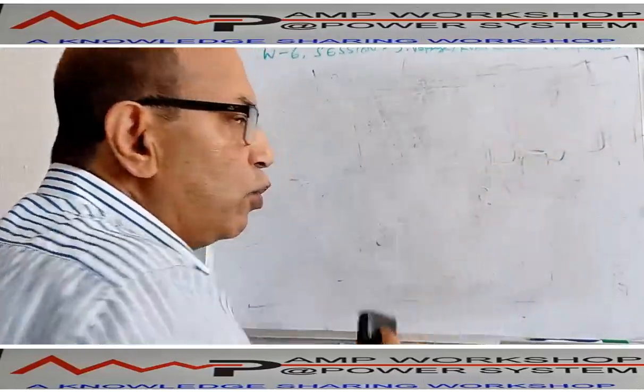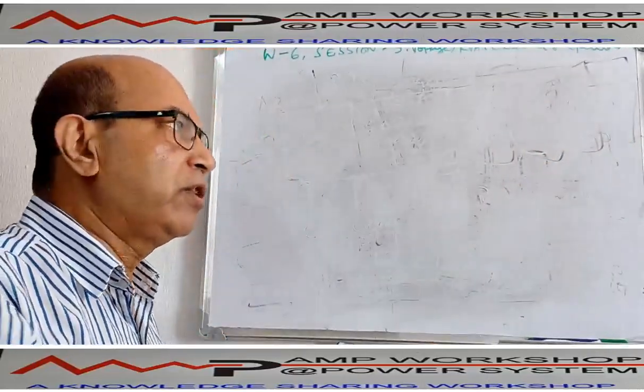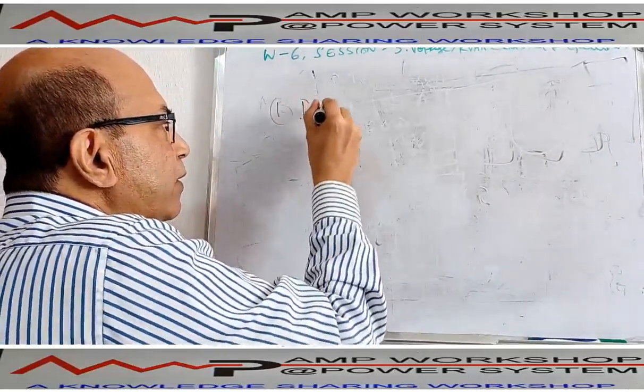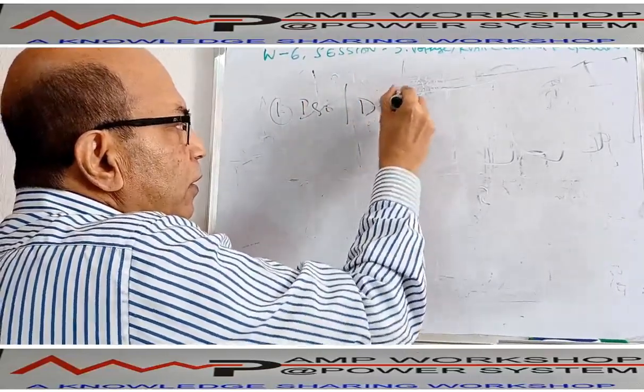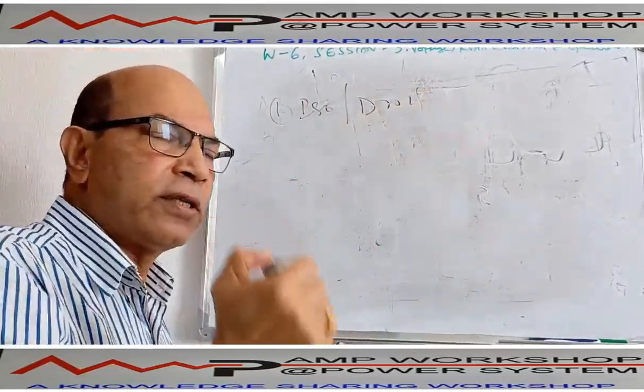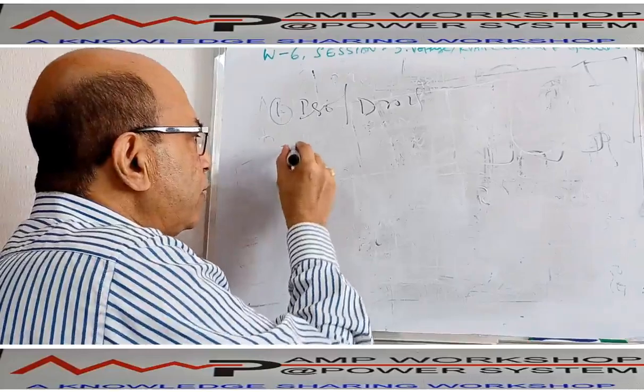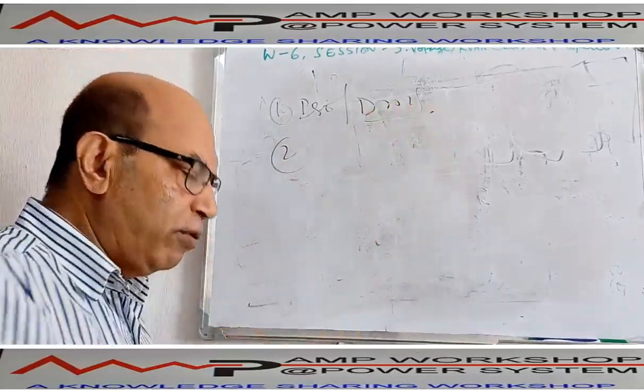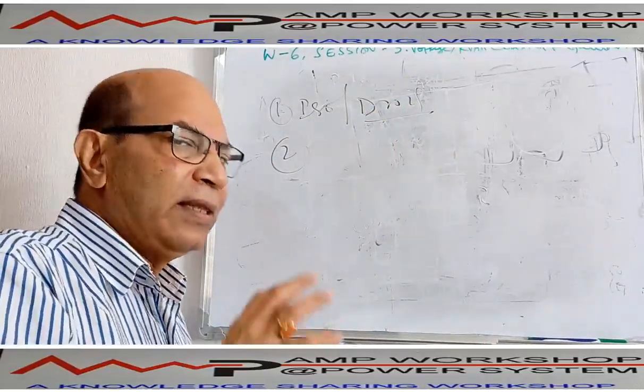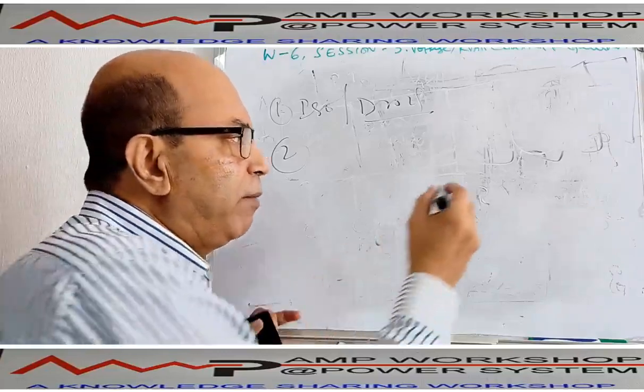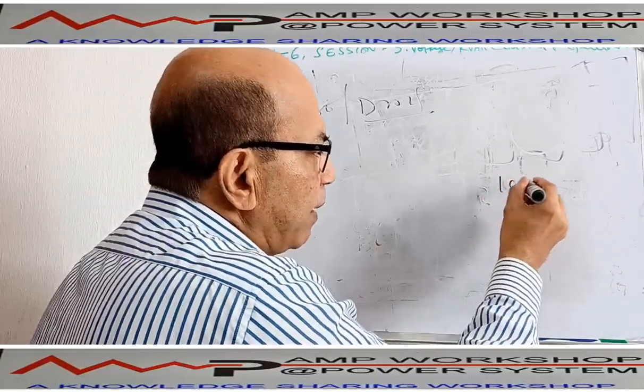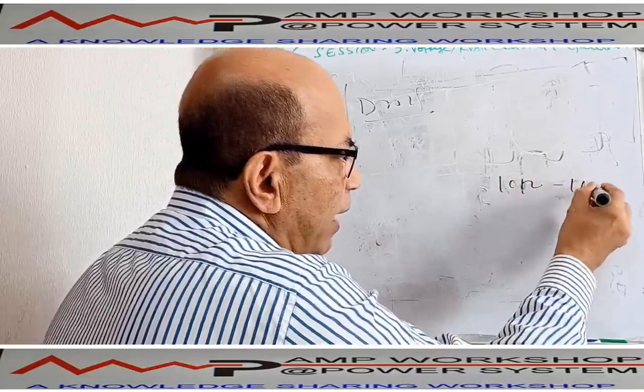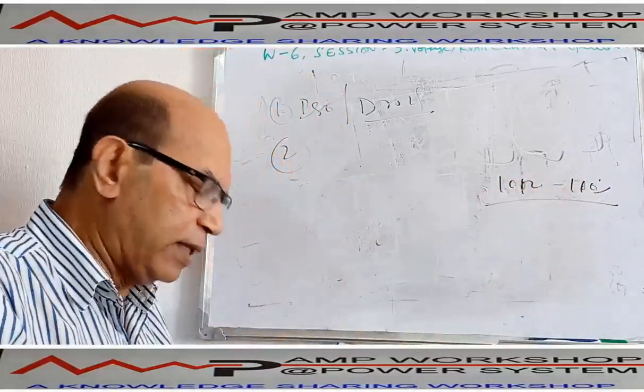The various settings which are available, obviously the first setting we need is the droop and isochronous mode selection. So there will be one setting automatically: one is isochronous or droop. That mode selection will be one switch. That is the first switch. Second switch, if you go for the droop, then the droop setting range is normally available from 100% to 110%. Speed droop and voltage droop, normally this is available.